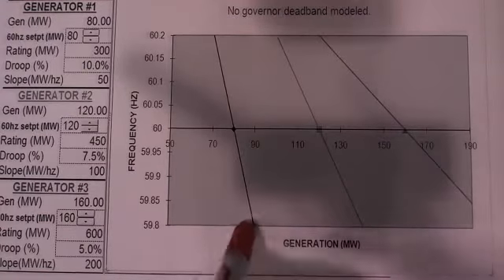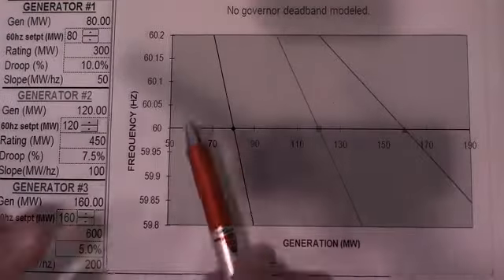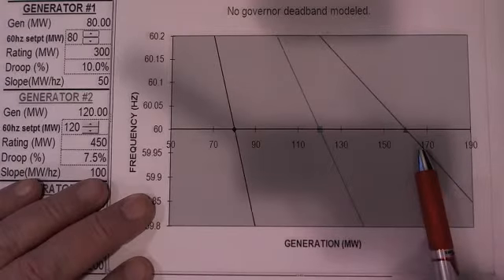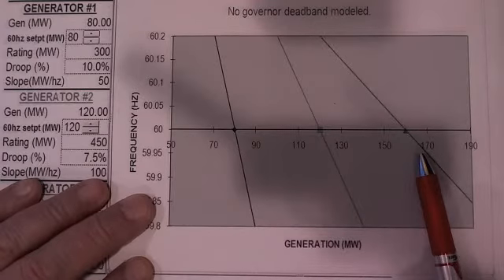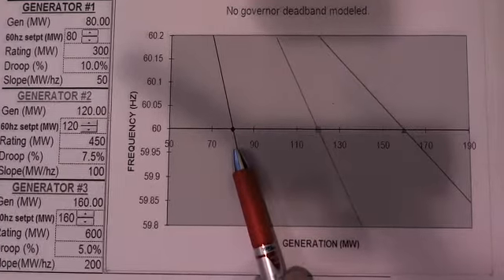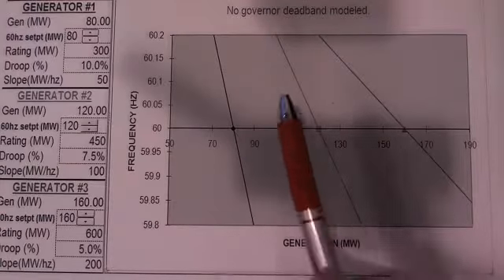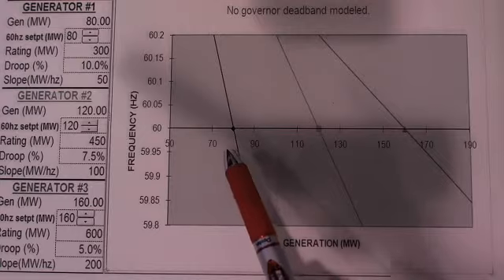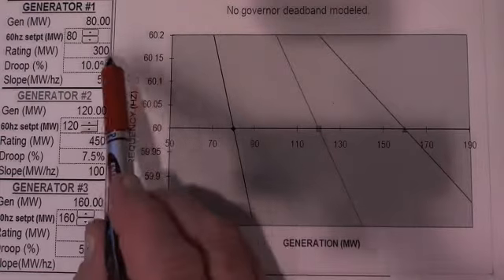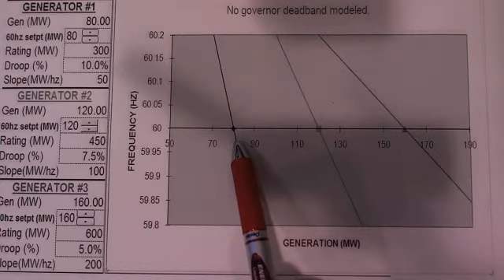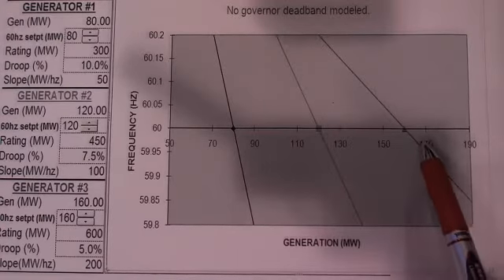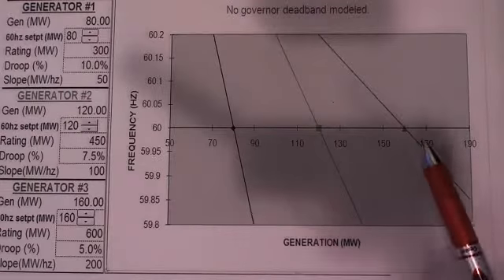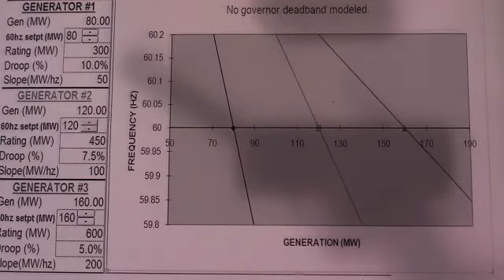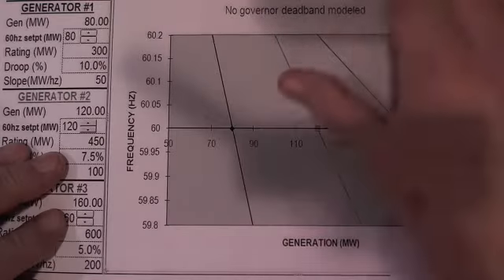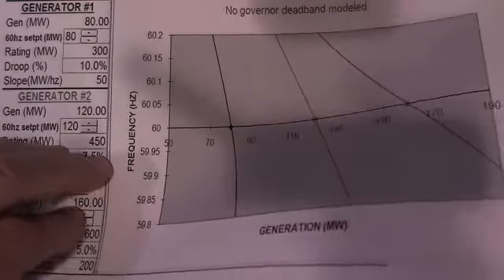This one, if suddenly the frequency changes, will get a large change in generation. This one won't get much change in generation. Typically, this would be a smaller generator, and that's what he's got up here. He says this is a 300 megawatt generator, here's a 450, and here's a 600 megawatt generator. So for a larger generator, the change in frequency will cause the valve to move, and you'll get a larger change in megawatt output. So it's all at steady state.